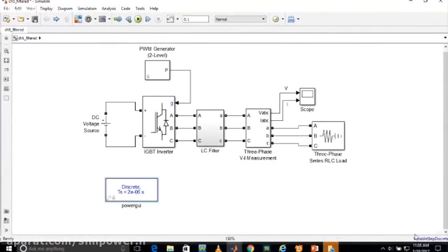So we have to go for a multilevel inverter circuit and then apply the filter circuit. Because after applying the multilevel inverter circuit, the harmonics present in the output of the inverter will be around 12%, 11% if we go for 11-level type. At that point, the harmonics present are only of 11th or 13th order, the highest frequency present in that signal.